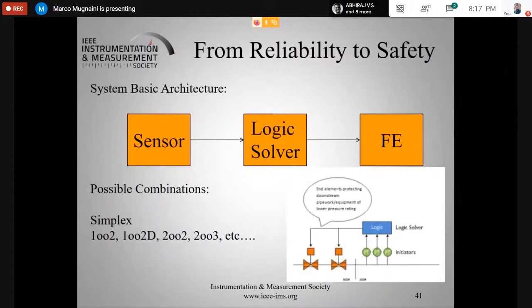So here, this is just to give you an overview of what's going on with safety. Of course, if you want deeper involvement in this subject, you have to consider that instead of a single block, the sensor can also be redundant sensors, the logic solver can be redundant logic solvers, usually placed in voting conditions, and the final element is usually not a single final element—it can be a series of elements, as depicted here in this function.